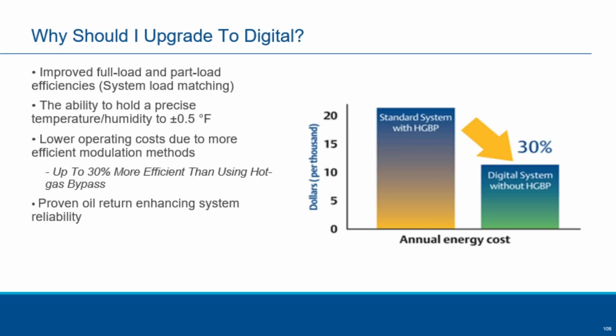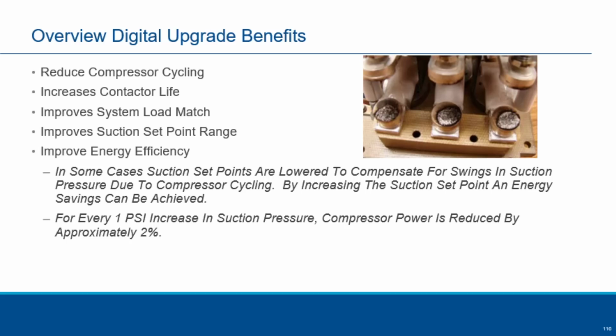So they used to use hot gas bypass, right? So now that compressor is fully loaded. A lot of energy usage. You go with the digital, right? Using the digital, that compressor's not fully loaded all the time. It loads and unloads, loads and unloads. Okay? And this is kind of what your contactors could look like. Instead of all those cyclings happening, you can reduce the amount of ons and offs, right?